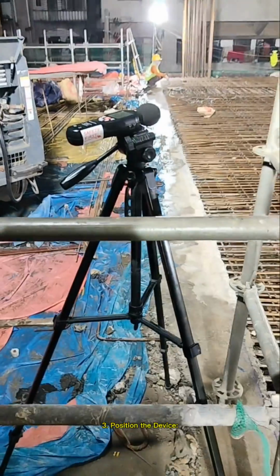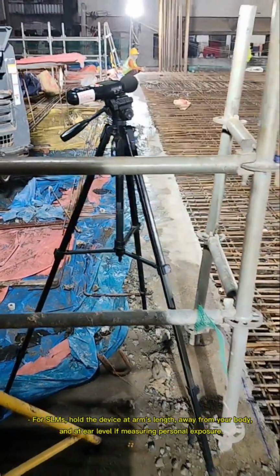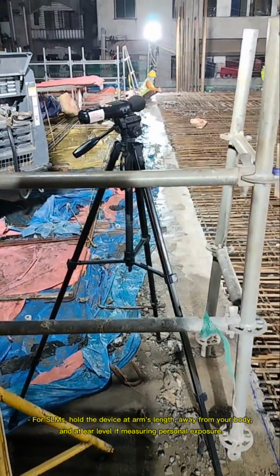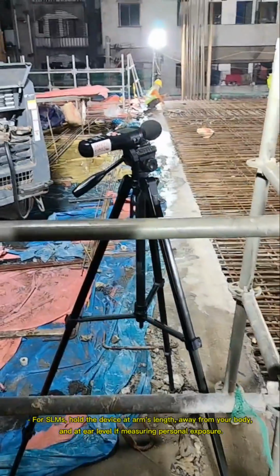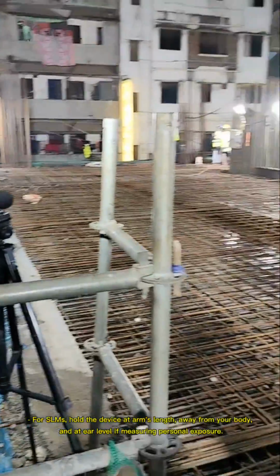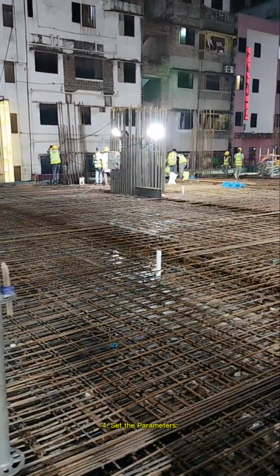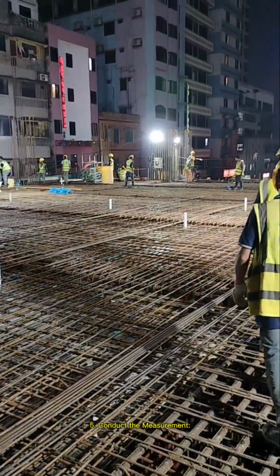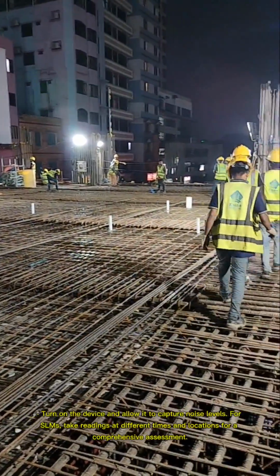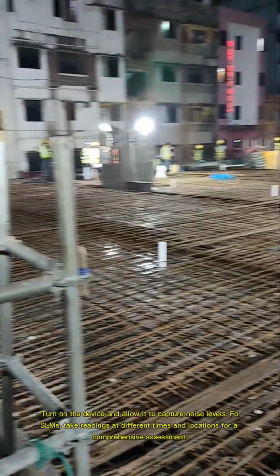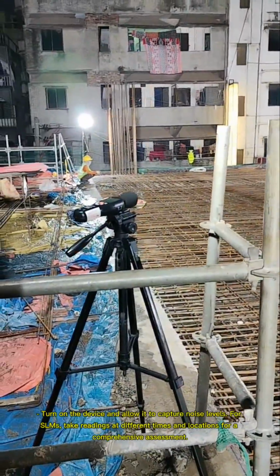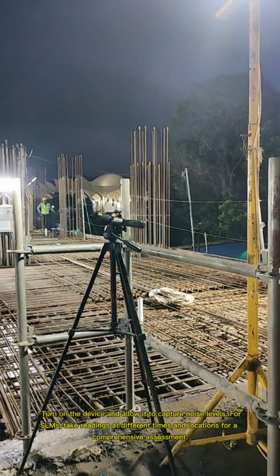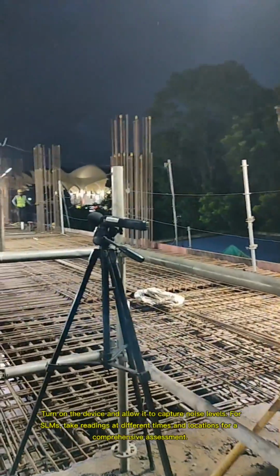3. Position the device. For SLMs, hold the device at arm's length, away from your body, and at ear level if measuring personal exposure. 4. Set the parameters. 5. Conduct the measurement. Turn on the device and allow it to capture noise levels. For SLMs, take readings at different times and locations for a comprehensive assessment.